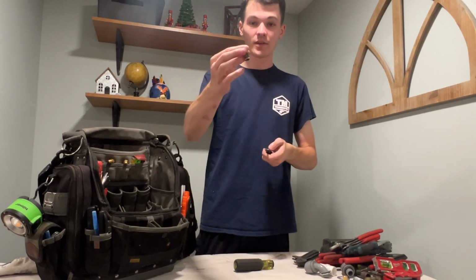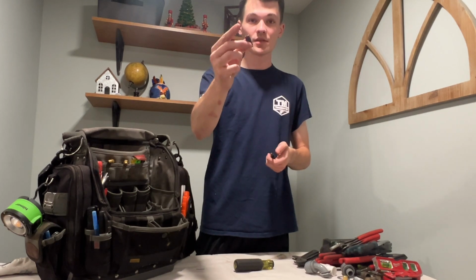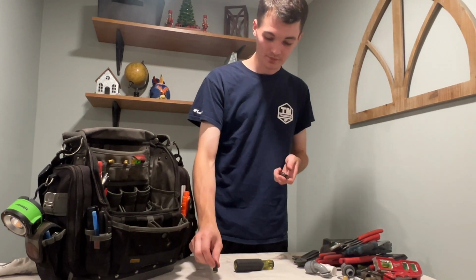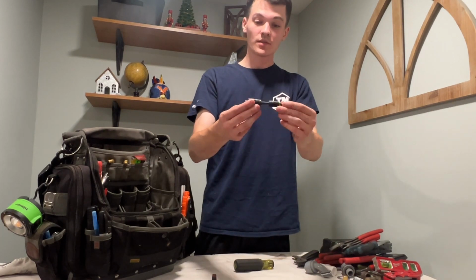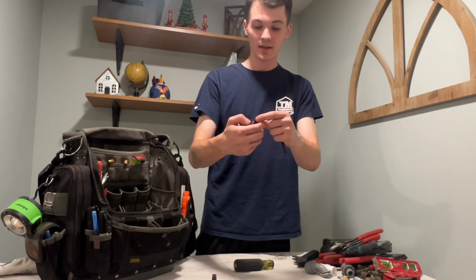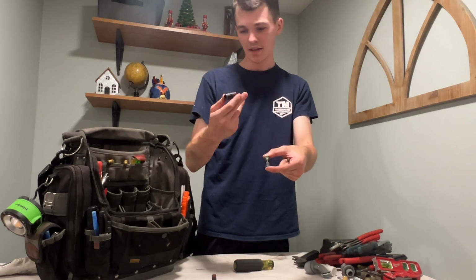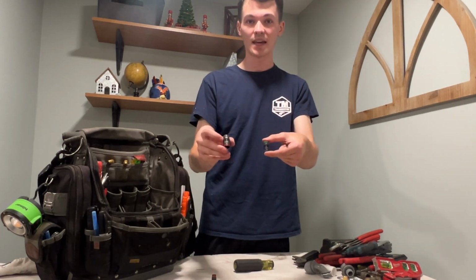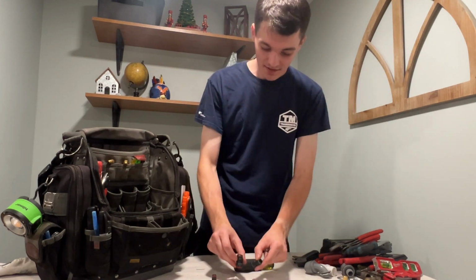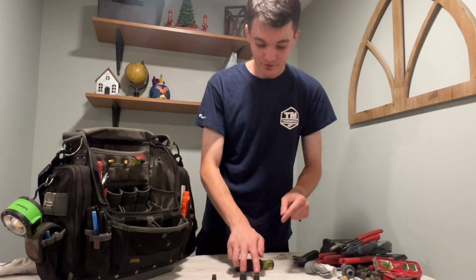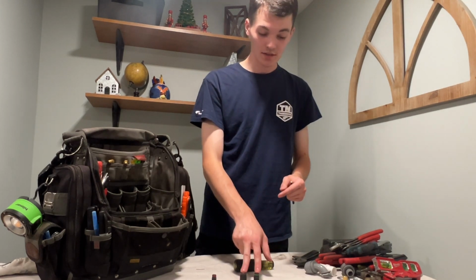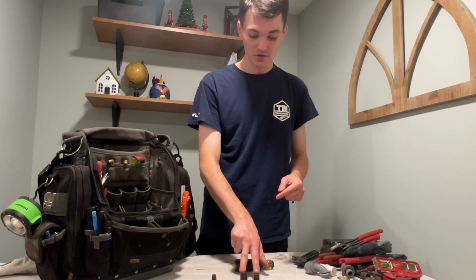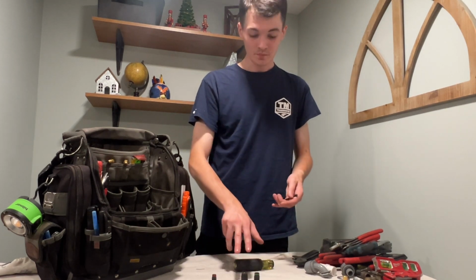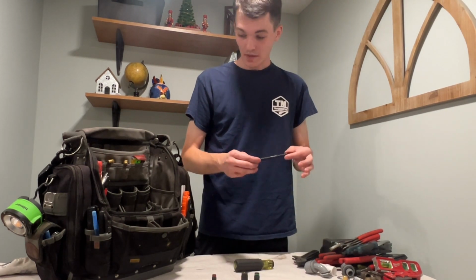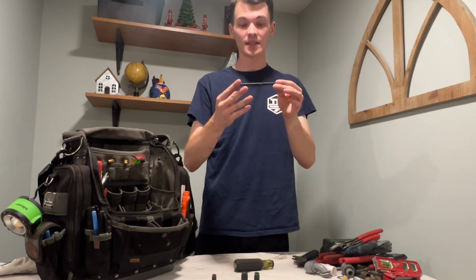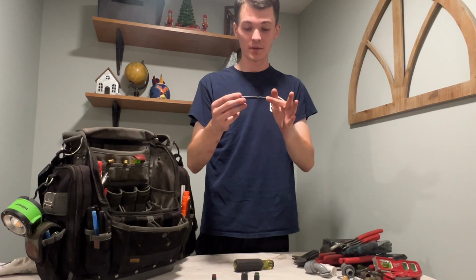If you pull off the first head that I have on here, this is your standard 1/4 inch and 5/16 that you use for every single unit. But if you pull off these larger heads, you have 11/32, 3/8, 7/16, and 1/2 inch. These two sizes are what you need for every blower motor or condenser fan motor I've seen in light commercial and residential applications. I use this all the time, and the benefit of having this head pull off is that you can slip it right onto your 1/4 inch driver on your impact gun.